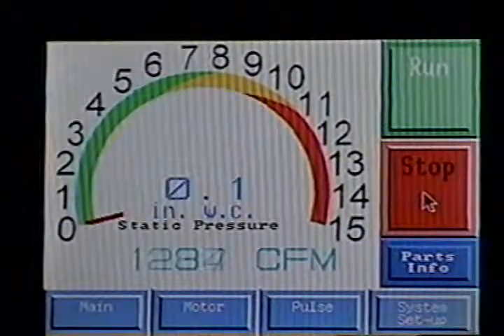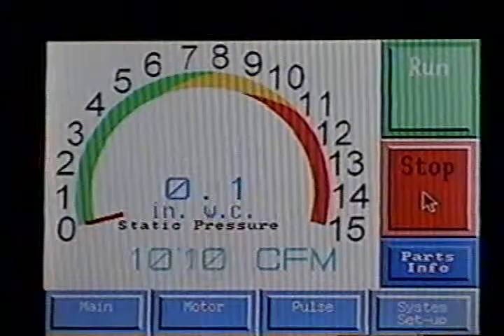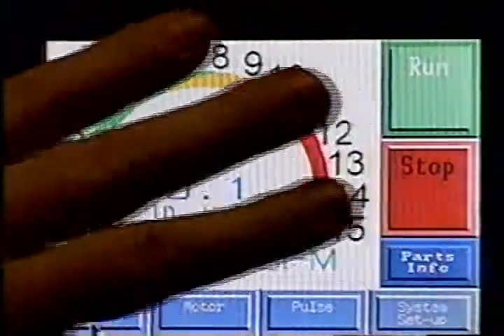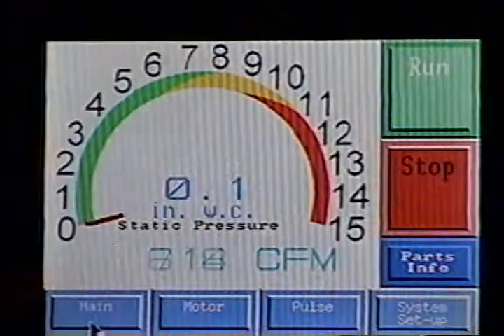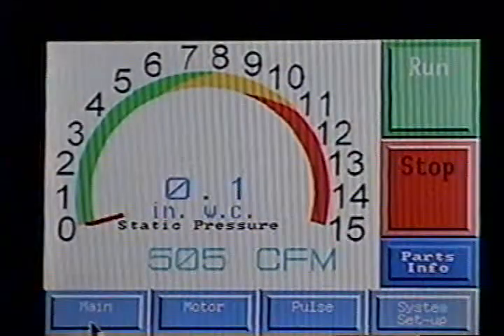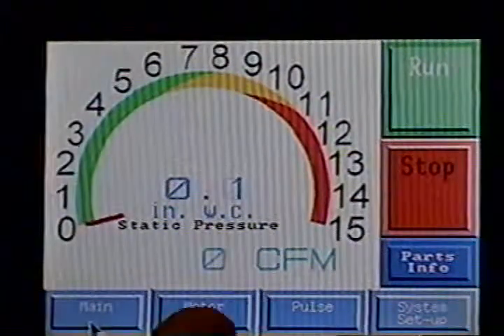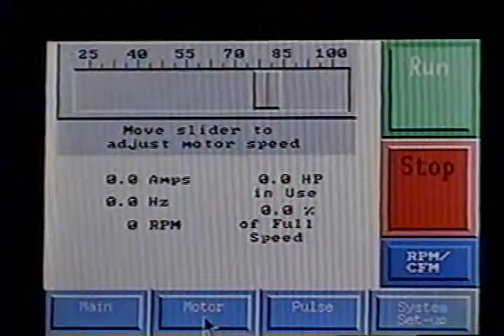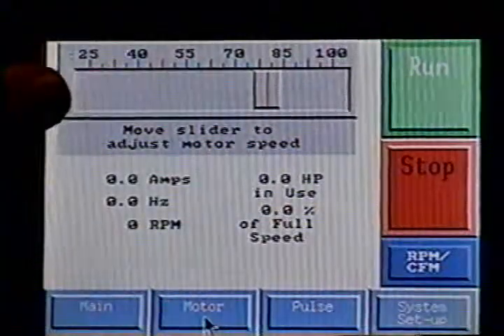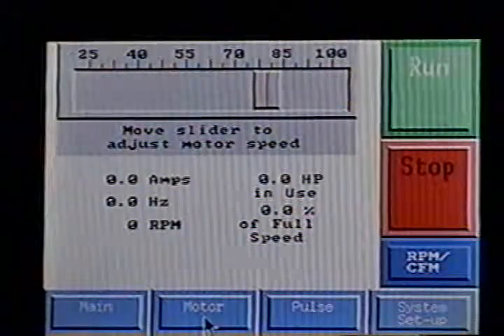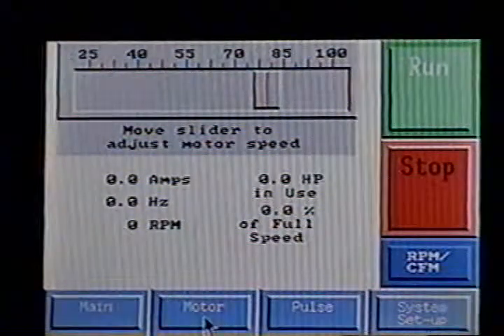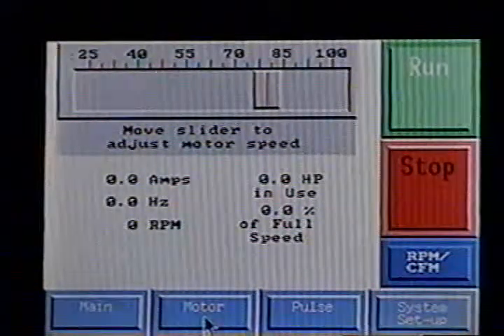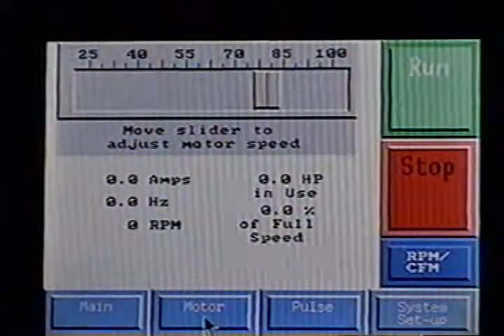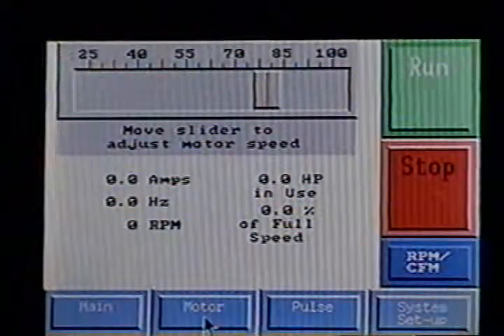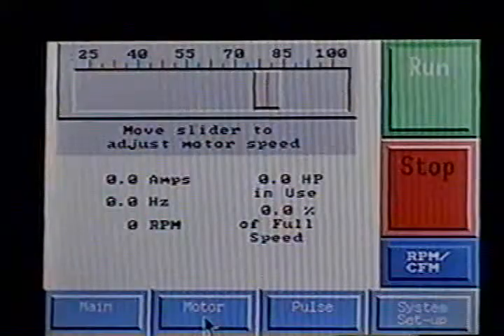I'm going to run through the other stuff that you can and can't do with it. Basically, you're looking at the main screen right here. You've got your static, you've got your CFM, you've got starts, stops, you've got access to other pages. The motor we kind of looked at, it's giving you the ability to adjust the motor purely based on what you want it to be on a 0 to 100% scale of the speed that you want it to run at. So if it's a 3450 RPM motor, you can tell it you want 50% of that, you can tell it whatever level you want.